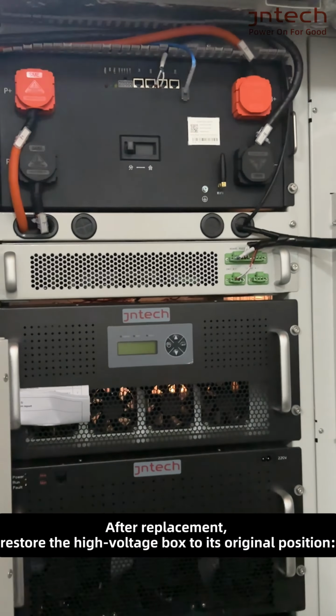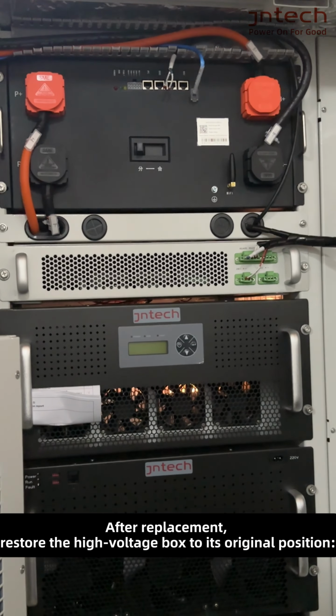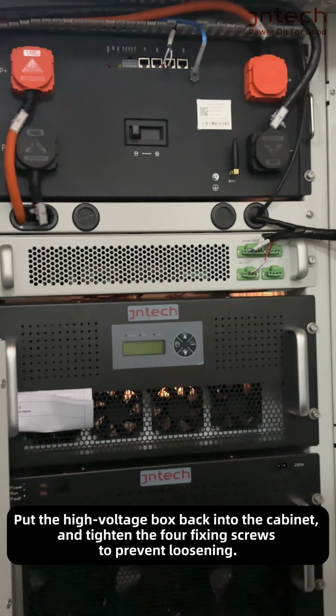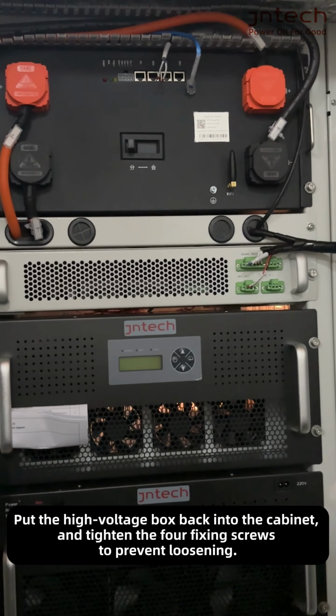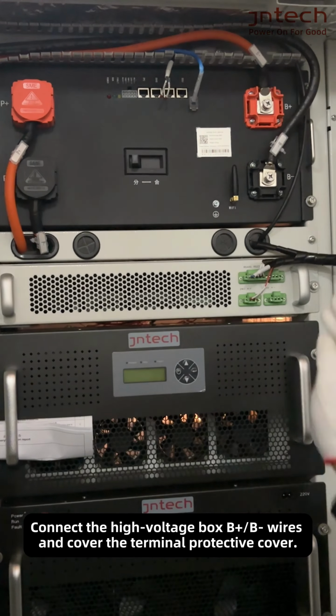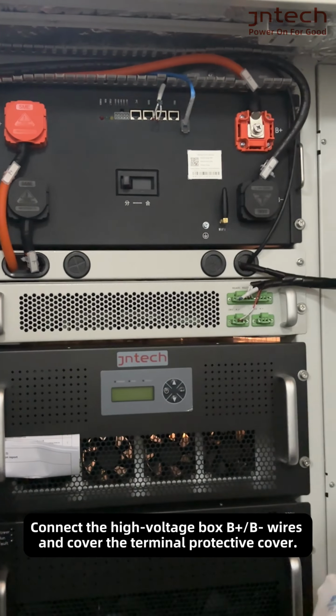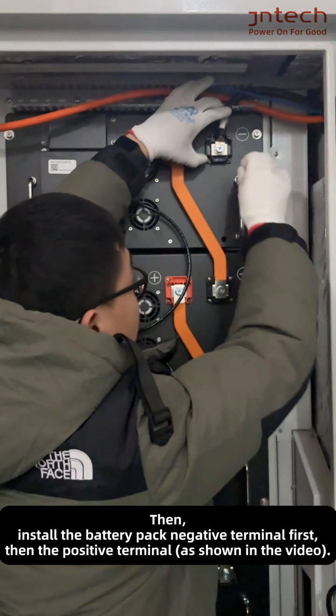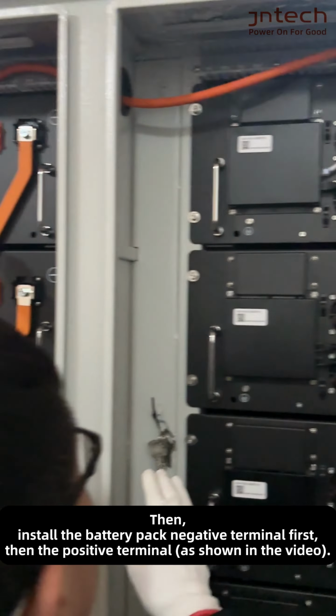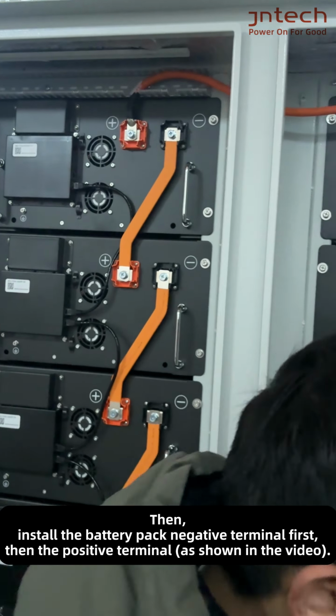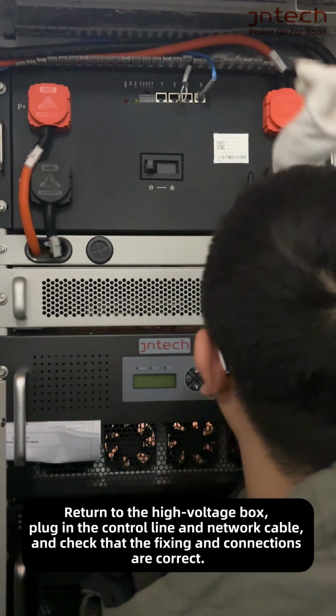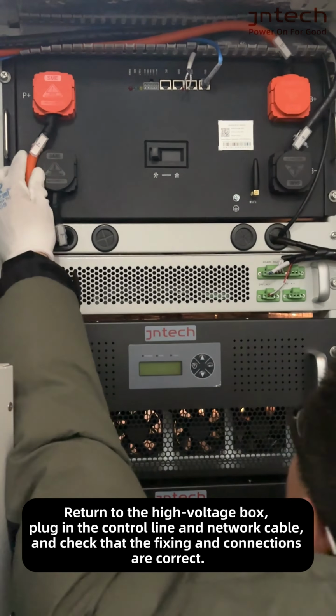After replacement, restore the high voltage box to its original position. Put the high voltage box back into the cabinet, and tighten the 4 fixing screws to prevent loosening. Connect the high voltage box B+/B- wires and cover the terminal protective cover. Then, install the battery pack negative terminal first, then the positive terminal, as shown in the video.